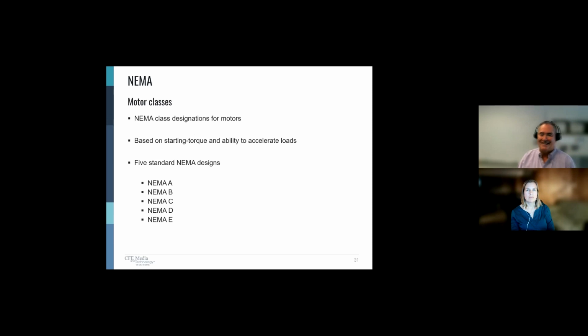We have motor classes. This one's a little more important for us when we're specifying new equipment. There are currently 5 classes, and they're based on starting torque and the ability to accelerate loads. Sometimes we don't care, especially in an air handler situation. The starting torque is pretty low, and we don't really care how fast it starts up. If it takes 30 seconds or a minute, we don't care, because typically in an air handler, once it's running, it's running. And I say there are currently 5 because as the industry changes, NEMA changes with the industry and adds classes as necessary.